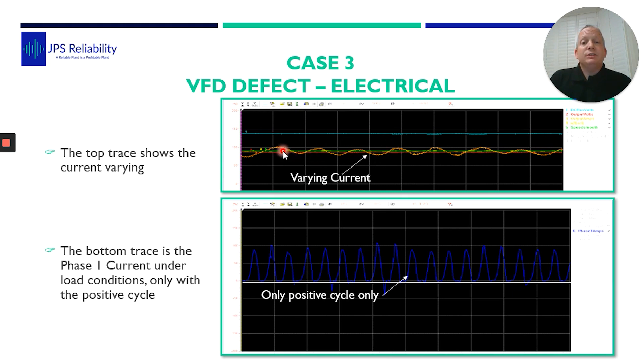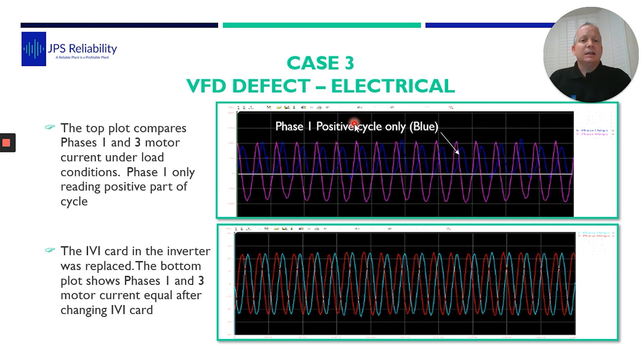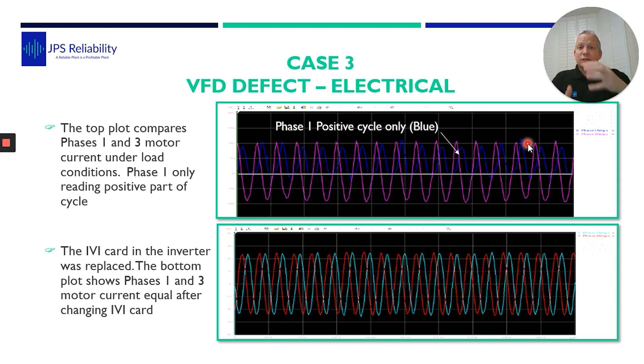Here is a current trace, and this orange plot is actually a varying current on this motor. When you look at the three single phases here, you can see there's only half a cycle on one of the phases to the motor on the three-phase supply. Comparing the two sine waves, you can see a full cycle and the blue line showing half a cycle. So that is why we were getting a warmer coil pack. And that is why we suddenly saw this 25 hertz — it wasn't happening consistently. We did some interrogation on the drive and found it was the IVI card.